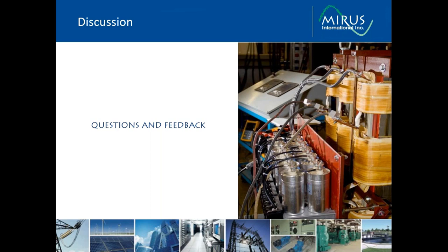Most passive filters, the weak point is the capacitors. In our design, we have designed it around a capacitor that performs much better in severe environments. We've been using this particular capacitor for the last 5 years, and I can proudly say that we haven't had one field failure on a capacitor in those 5 years. So we expect that to continue. But it is important, in a passive filter design, to ensure that the capacitor is a robust capacitor and one that can stand up to the rigors of real-world applications, which include background voltage distortion and voltage imbalance.